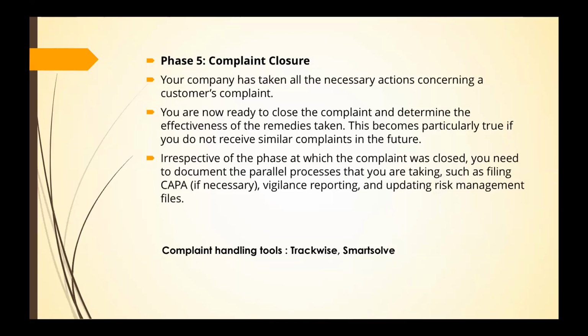So irrespective of the phase at which the complaint was closed, you need to document the parallel processes that you are taking, such as if the CAPA, corrective and preventive action, is necessary, if the vigilance reporting is necessary, and also updating the risk management files. So this is what happens, these are the steps that they take for closing any complaints. Closure is not done just like that, they have to justify each and every line item: what they have done, what action item they are going to take, and how they are reporting it.